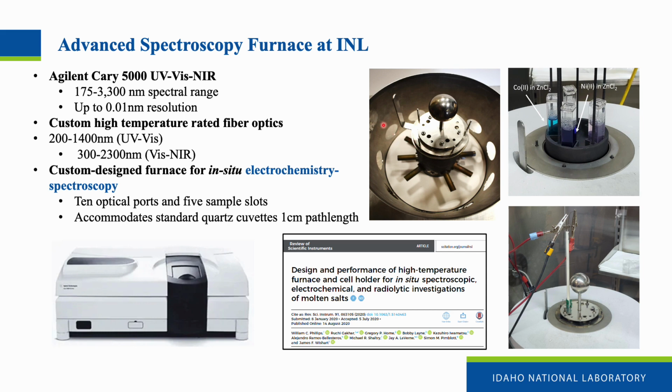We do optical spectroscopy in transmission mode, in the UV range and in the near IR range, using a spectrophotometer outside the glove box. We also have Raman spectroscopy that we do in reflectance mode using the 5th port, and we still have space for combining other spectroscopy approaches here.